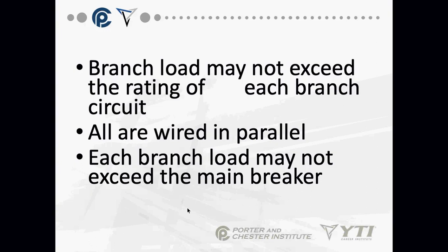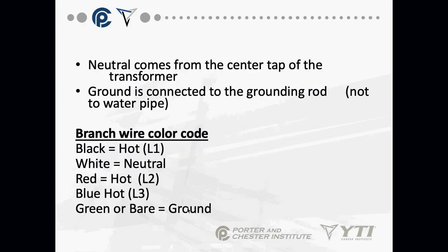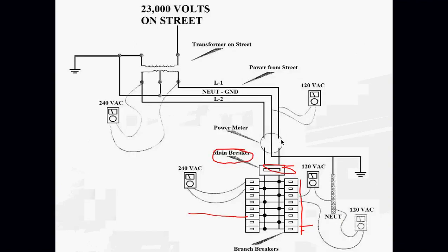Okay, we don't want one load to go out and take out the entire circuit, so everything we do is wired in parallel up to where we deal with control circuits and circuits inside equipment. Each branch load may not exceed the load of the main breaker. So if I come back to this page here, if I have a 200 amp main breaker, my loads on the branches cannot go over 200 amps.